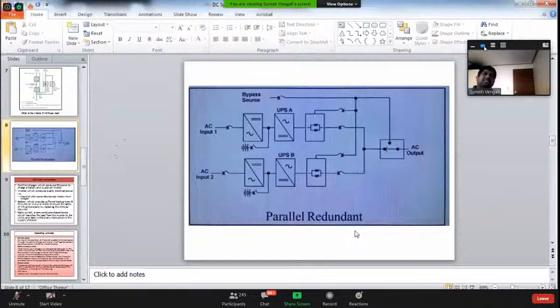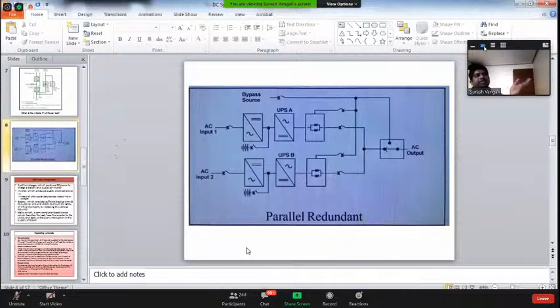Some people may say trickle charging, some people may say float charging. Ultimately, trickle charging is the trickle current - you can say trickle current is that to maintain the battery. A battery manufacturer, if you ask him, will say trickle charging because the trickle current is required to maintain the healthiness of the battery. But because the battery manufacturer is different and the UPS manufacturer is different, the UPS manufacturer will call it float charging. So the terminology differs between the two.